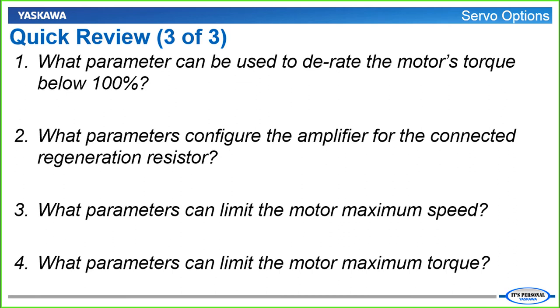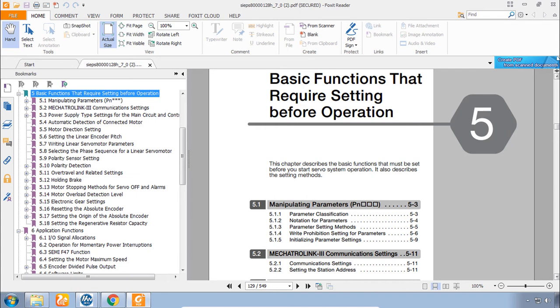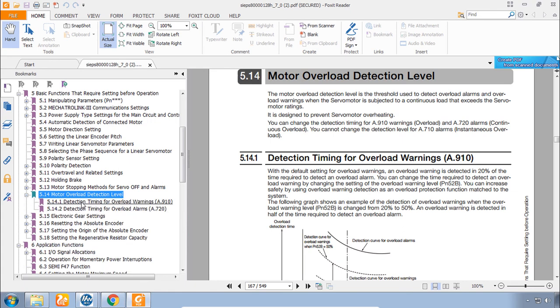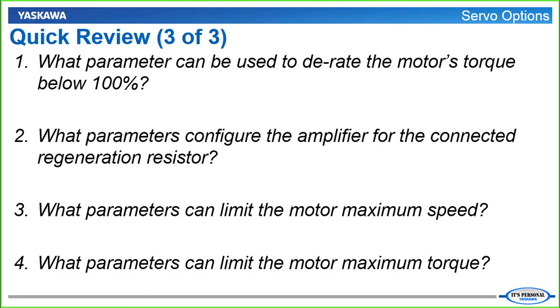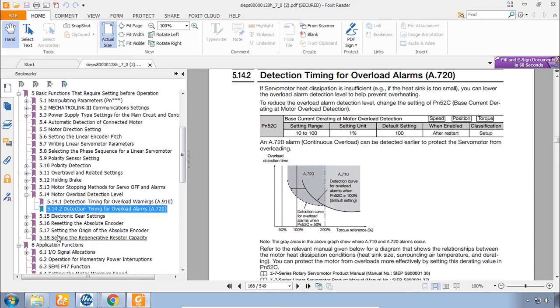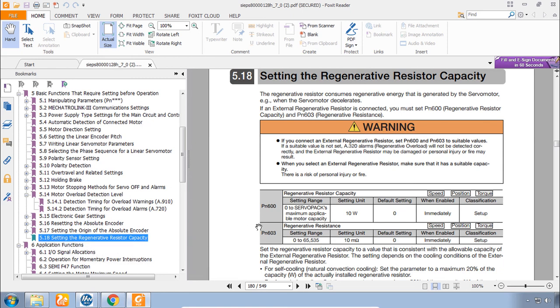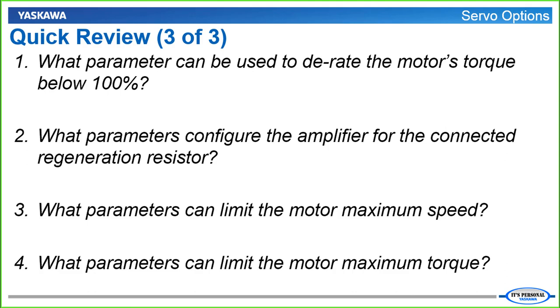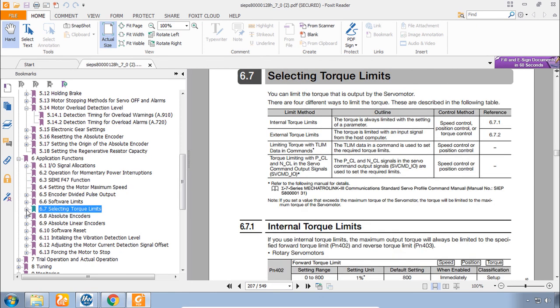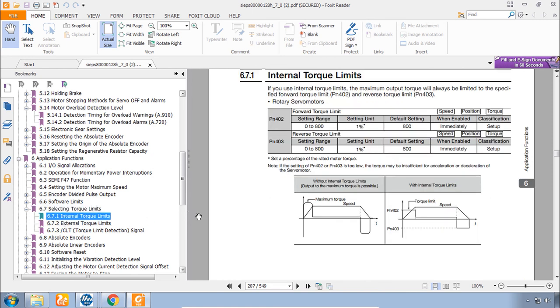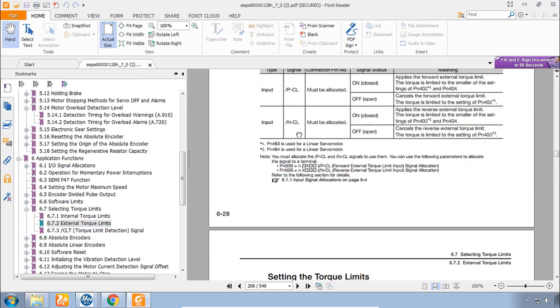OK, number one. Derating the motor's torque below 100%. That's in section 5.14. And it's not the overload warning time. It's called detection timing for overload alarms. Parameter PN52C is the answer. Number two. Configuring the regen resistor. That's a couple sections down in 5.18. And the parameters are PN600 and PN603. Number three. Parameter to limit motor's speed. We find that one down here in 6.4 setting motor max speed. And it was parameter PN316 for rotary and 385 for linear. And parameters to limit max torque. Max torque we skip down here to 6.7. Torque limits. With the internal torque limits set with PN402 and 403. Active always although they can be changed by the controller. And external torque limits activated by inputs. In PN404 and PN405.